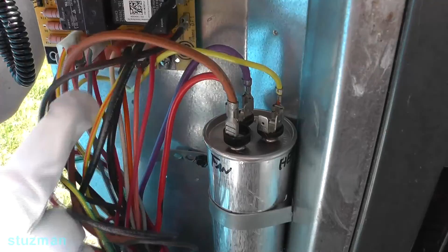Also, this on the back here with the yellow wire is going to be my Herm. This is for hermetic compressor. This is also going down to the start or auxiliary winding for the compressor. Now this final terminal over here, we got a red wire and we have a purple wire. This is a common terminal. This common terminal means it's common to these two capacitors.